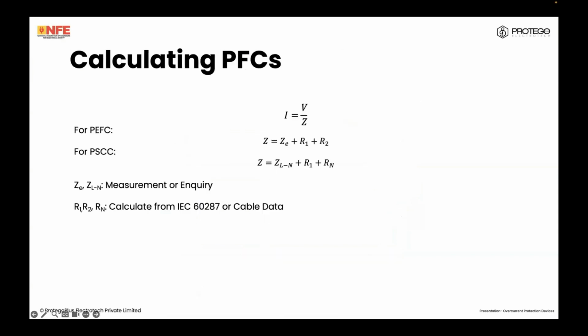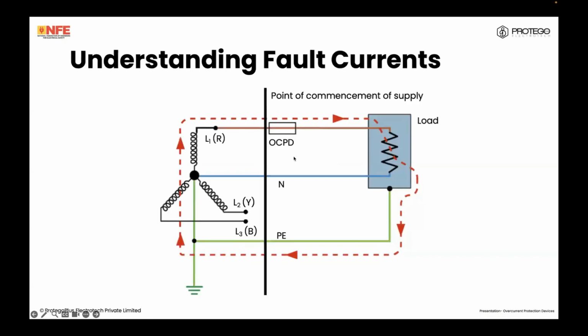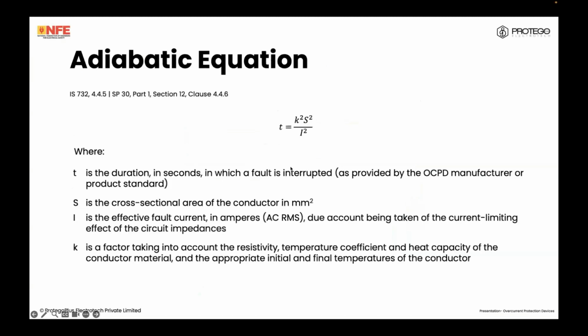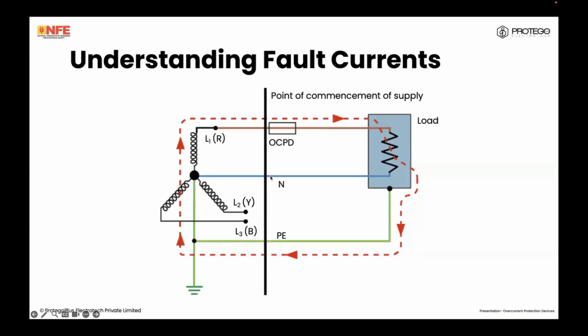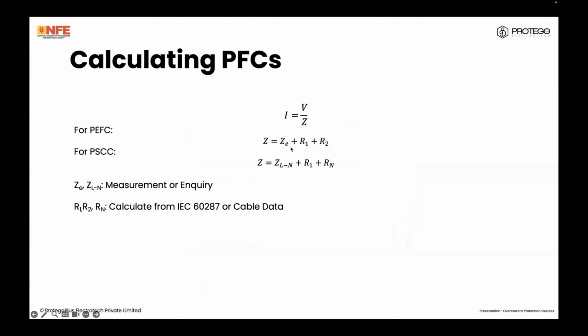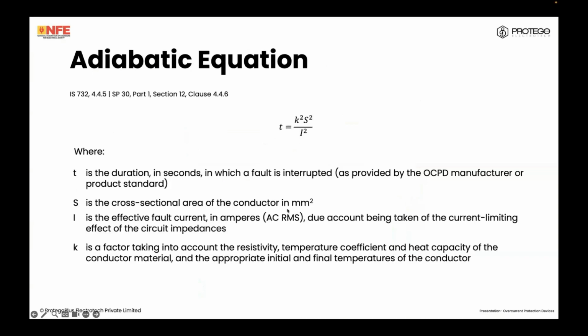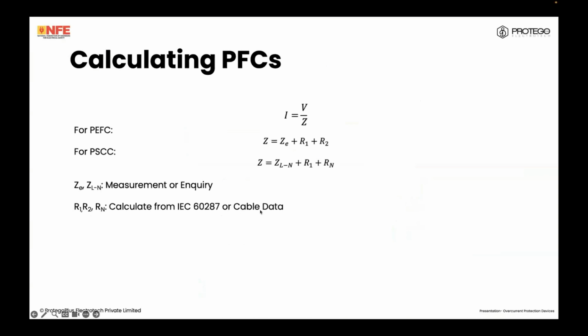How do we calculate this? Basic Ohm's law, I is equal to V by R, we'll just substitute it by Z. For earth fault current, this is the earth fault loop impedance at the source plus R1, which is the resistance of the line conductor, plus R2, which is the resistance of the protective earth conductor. For prospective short circuit current, it is loop impedance between line and neutral plus R1 plus Rn. This value ZE, ZLN, the loop impedance for short circuit and for earth faults, can either be measured or inquired or calculated based on the transformer if you have that. R1, R2 or Rn can be calculated from IEC 60287, but if you buy your cables from a good manufacturer, this data will be given to you.